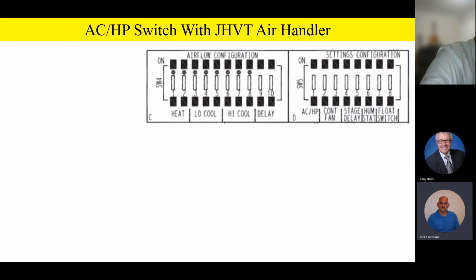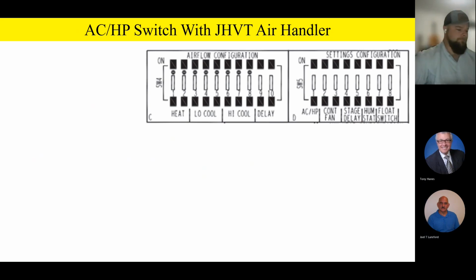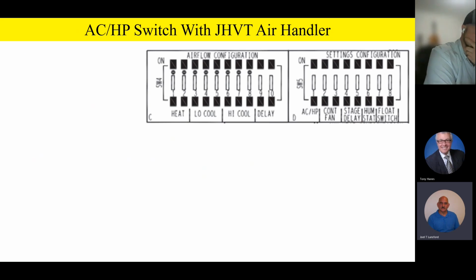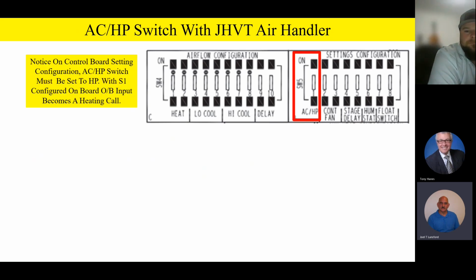All right, as we take a look at the airflow configuration and the system setup dip switches, you're going to notice that on the control board itself, there's going to be a bank of dip switches. You're going to have some airflow configuration, some system setup configuration, and some different things on there. But specifically, we're going to drill into one particular dip switch this morning that we want to talk about. And that's the AC/heat pump switch.